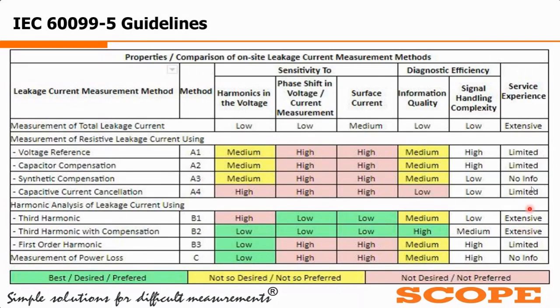Also, you can see over here, these two methods have been mentioned by IEC itself as having extensive service experience. And for the C method or A4 method, there is very limited information or no information available. Out of the others, we are using the voltage reference or the A1 method, and we are bound to use it in some specific cases, like GIS application, when we will not be able to use the B2 method or B1 method.